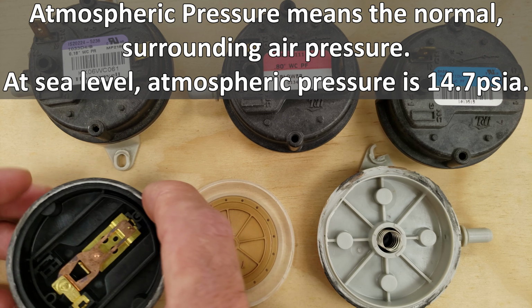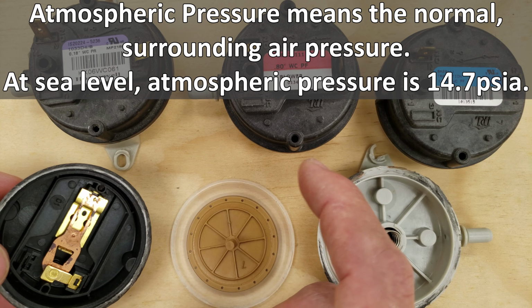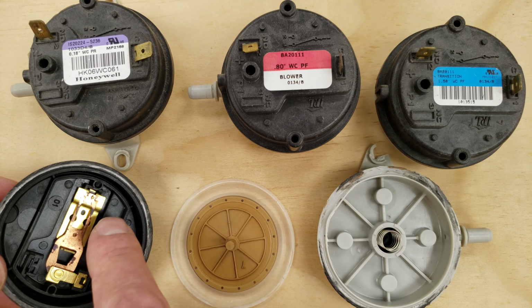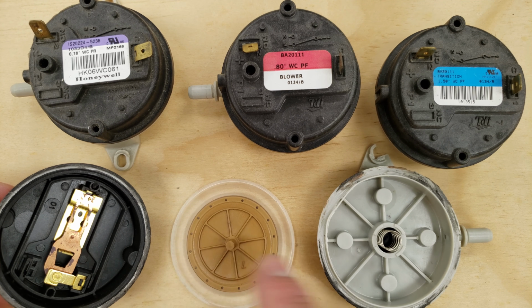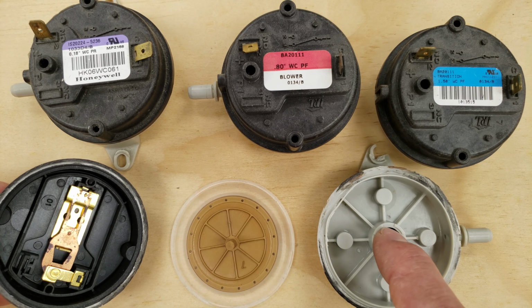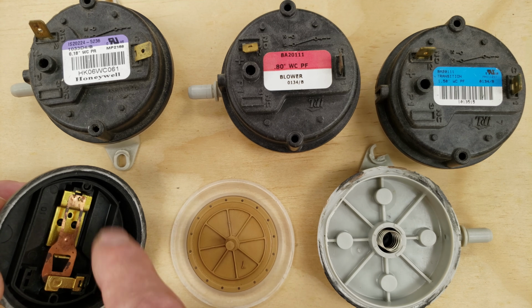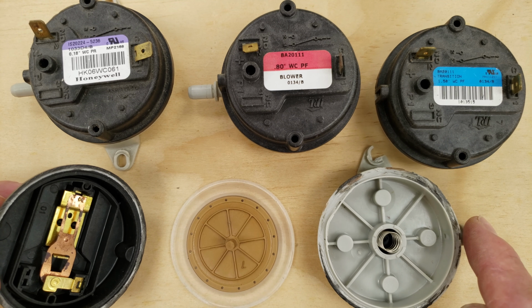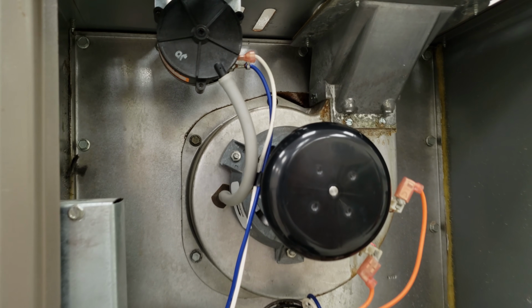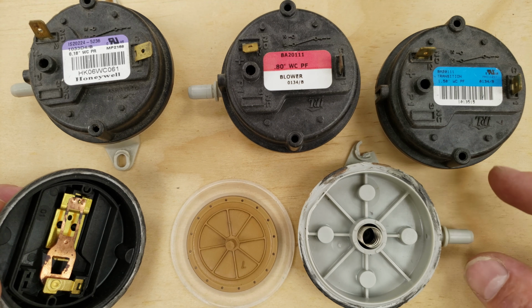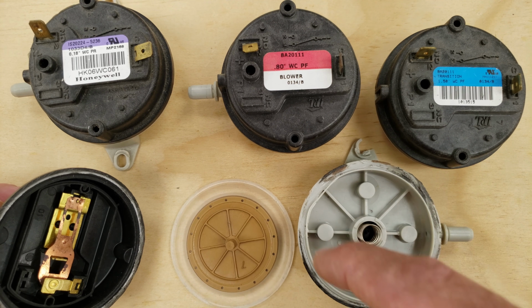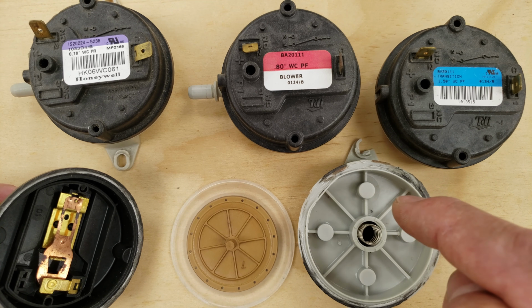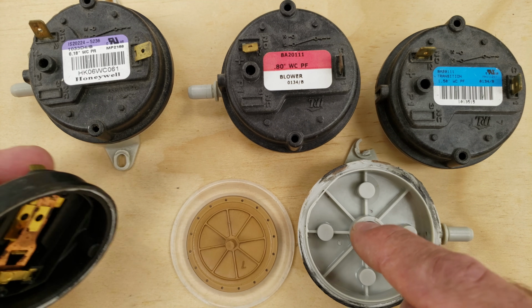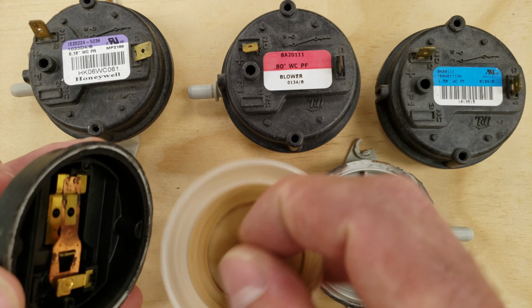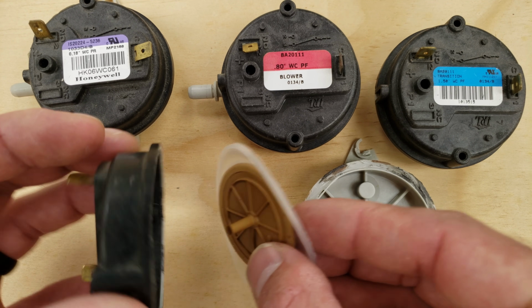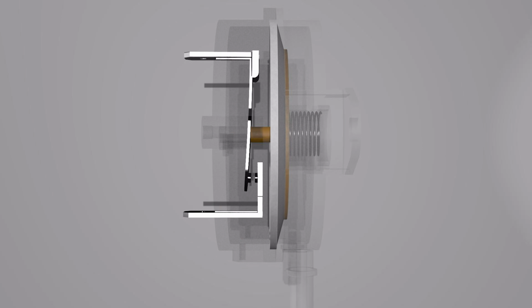And I'll get to the two-port pressure switches in just a little bit. I just want to make sure that you understand what's actually happening. You have atmospheric pressure on this side, and this side has atmospheric pressure plus the spring pressure. So it's always greater than the atmospheric pressure over here when the inducer motor is not turned on. Anytime that the inducer motor, which is connected to this little port right here, is turned on, you're reducing the pressure in this chamber. And so this pressure plus the spring pressure is less than the atmospheric pressure on this side, and then this diaphragm lets go on this switch right here, and then the switch closes.